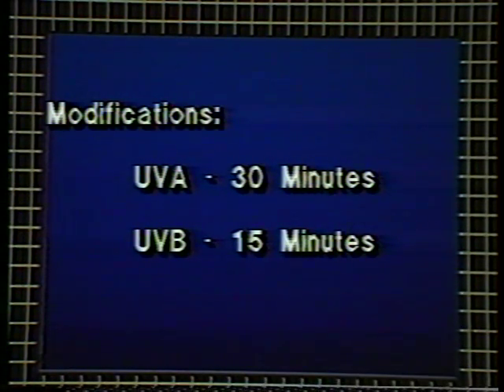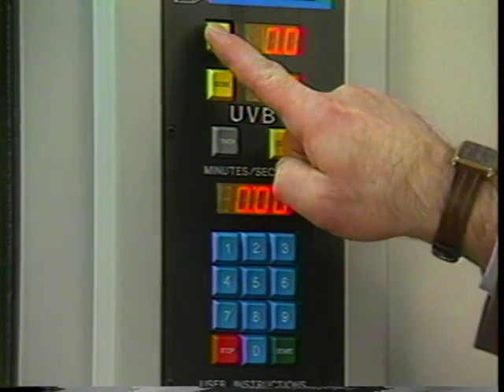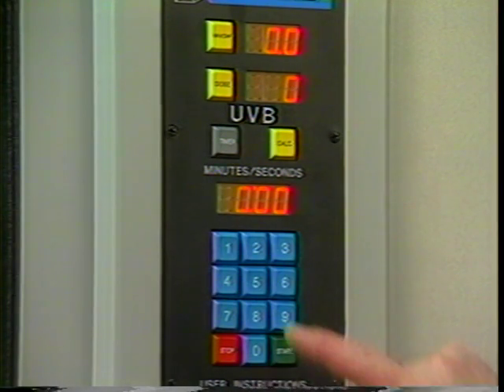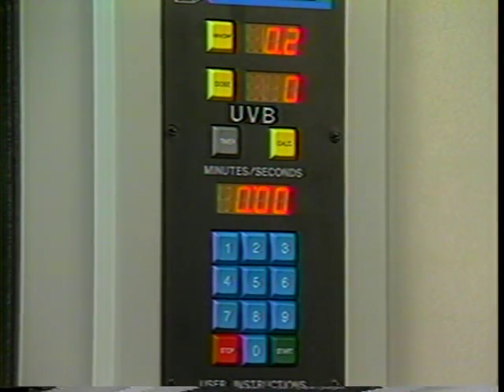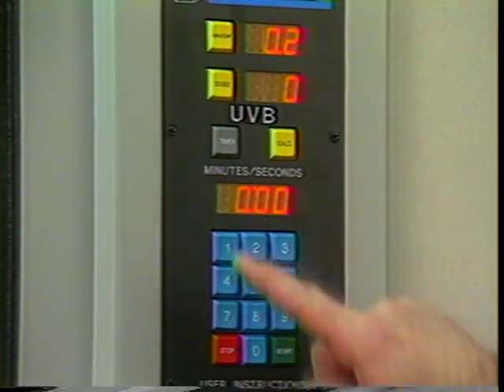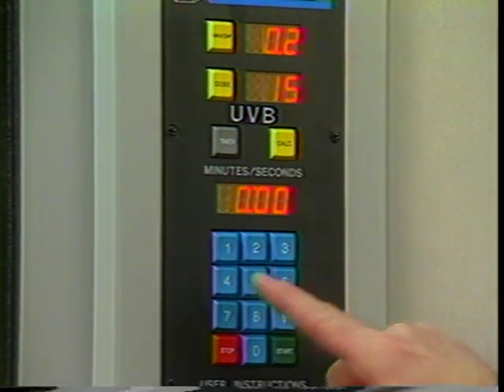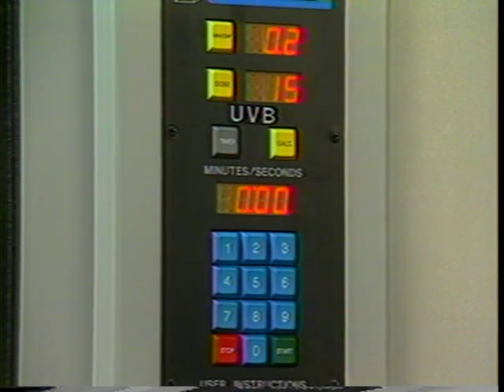Conversely, the low-end limitation is normally determined by low lamp output readings. If the UVA lamp output reading is below 7.0 milliwatts per centimeter square, or the UVB output reading is below 0.3 milliwatts per centimeter square, the timers will not calculate a treatment time. A series of dashes and a capital L will appear in the bottom display window. Low lamp output readings indicate that the HOUVA II system should be relamped.